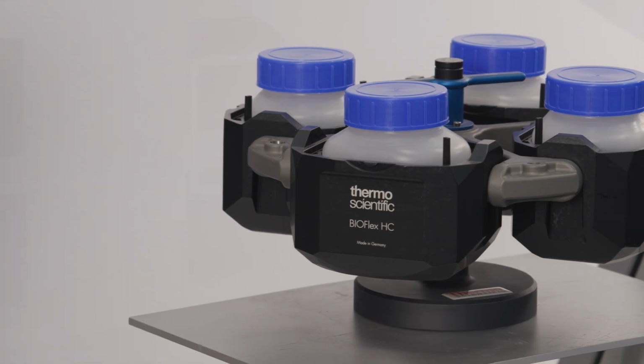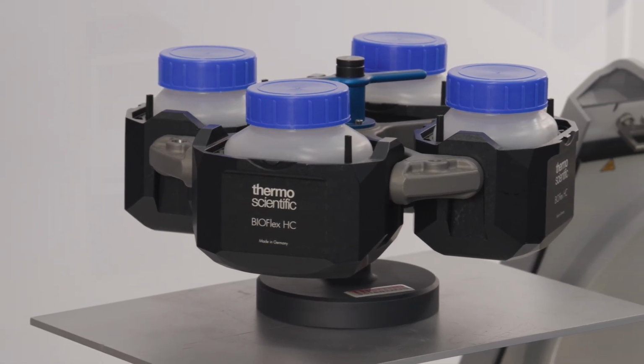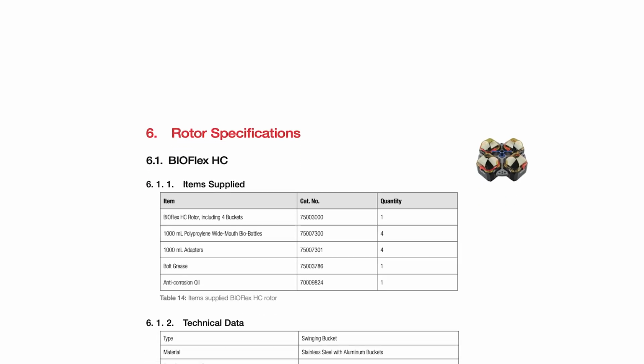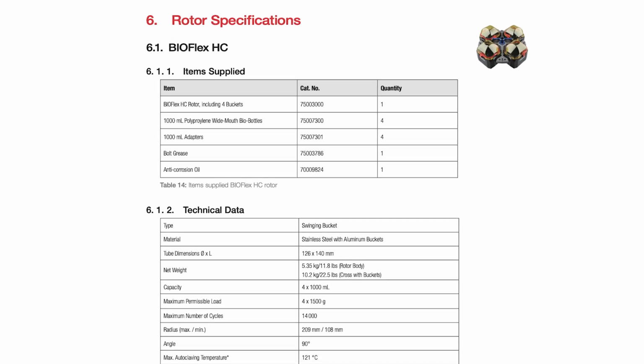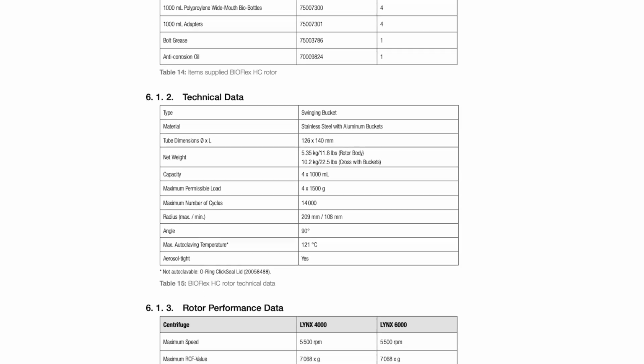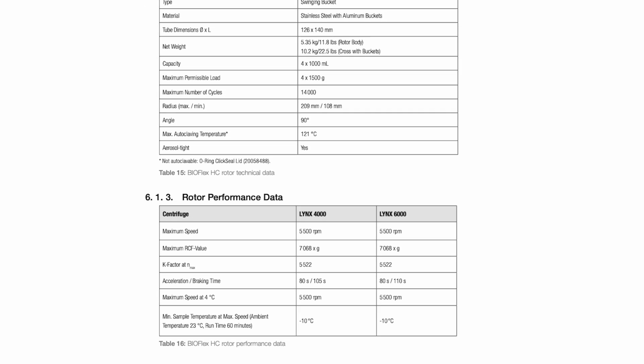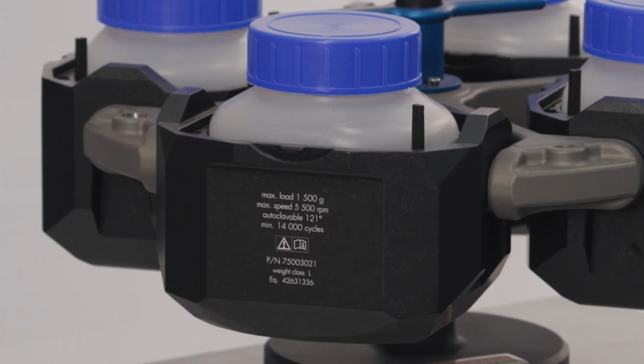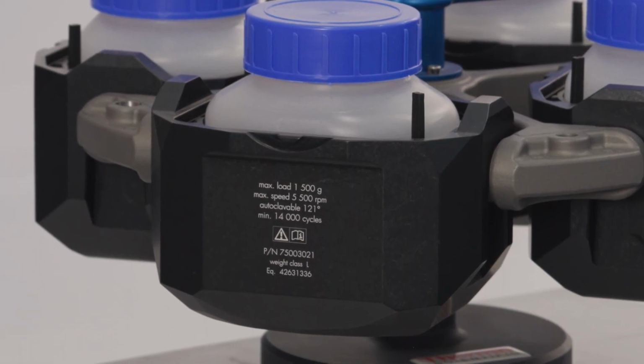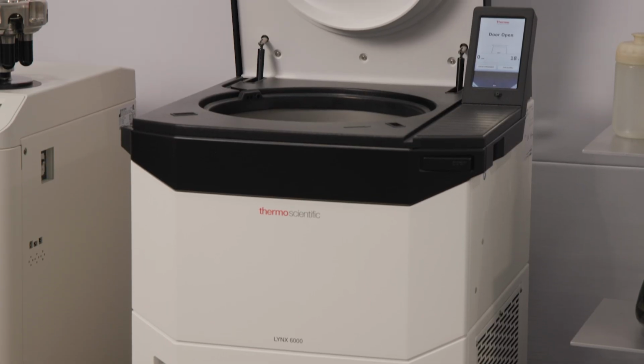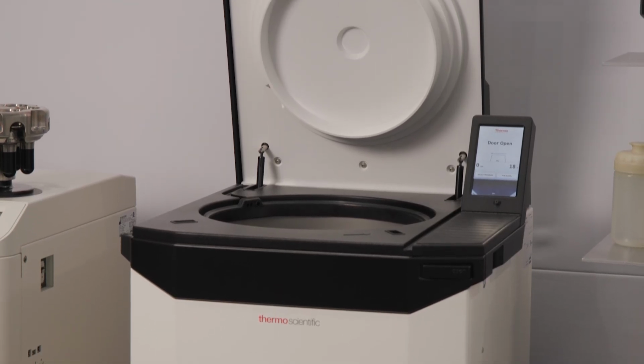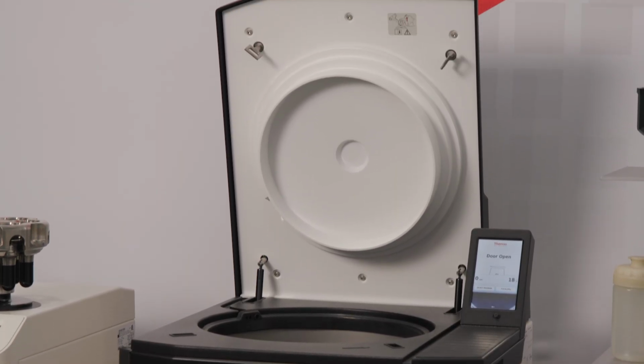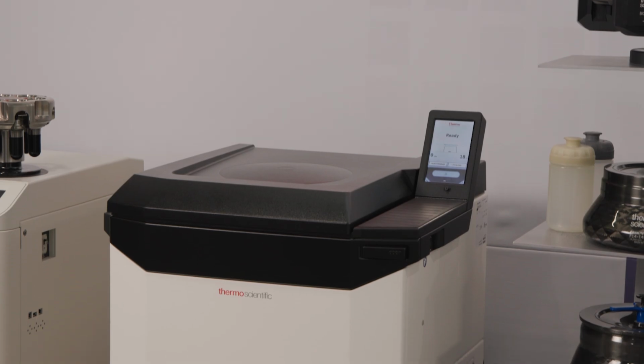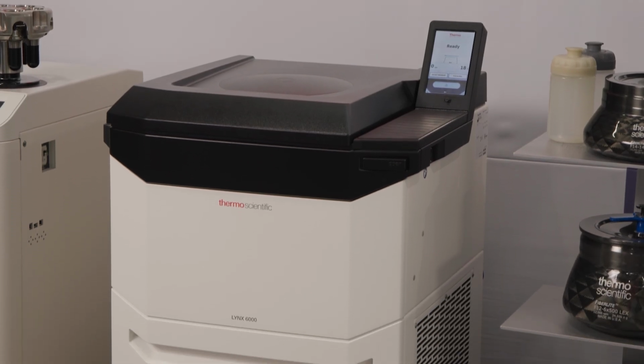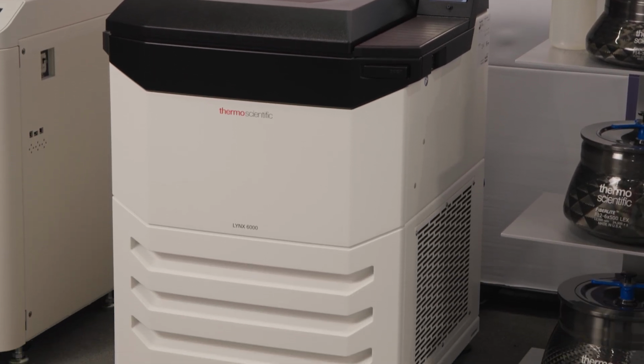The lifetime of a rotor and buckets depends on their physical load. You can find the maximum number of cycles for rotors in the instruction manual's rotor chapter. Do not use rotors and buckets that exceed the maximum number of cycles. The maximum number of cycles is marked on the bucket. Replace vacuum pump vanes every 4,000 hours or 5 years for reliable performance. It's recommended to have an authorized technician service the centrifuge and accessories once a year.